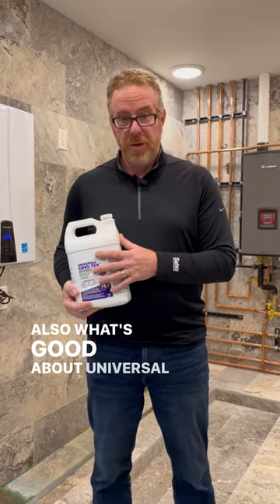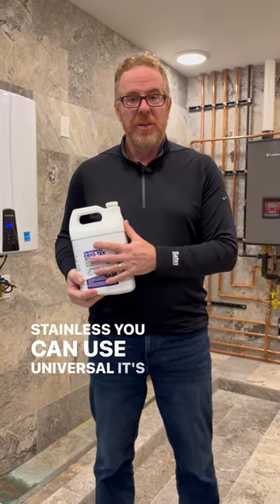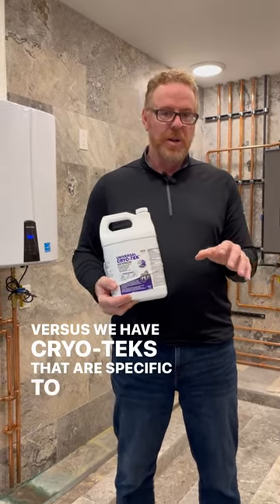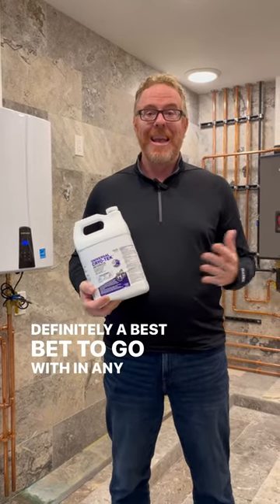Also, what's good about Universal is that if you don't know what metals are in your system — be it aluminum, galvanized, or stainless — you can use Universal. It's good with all of them, versus the Cryo-Teks that are specific to aluminum or specific to stainless. If you're not sure, Universal is definitely the best bet to go with in any case.